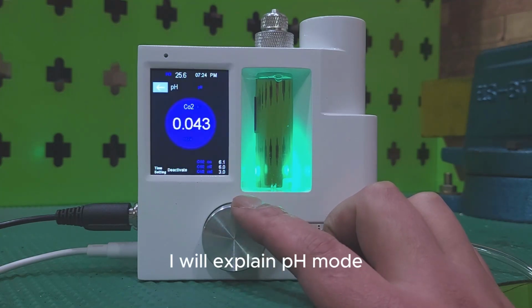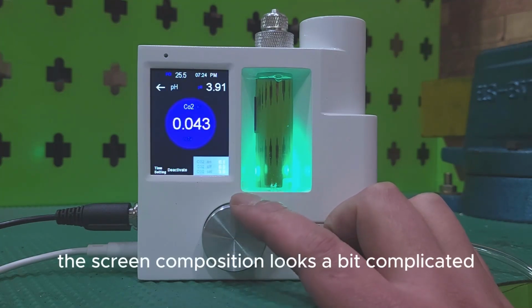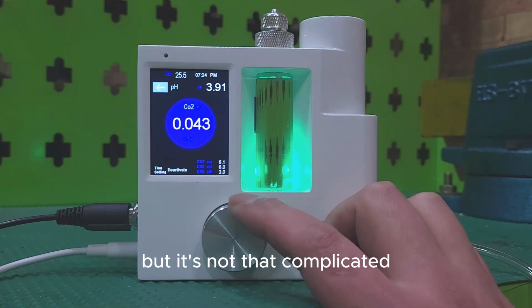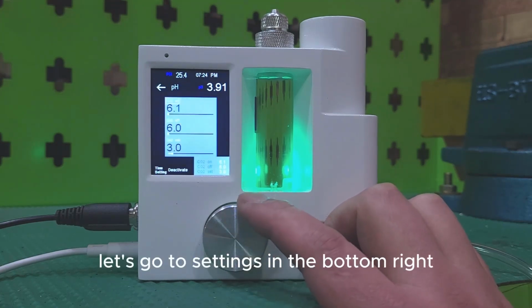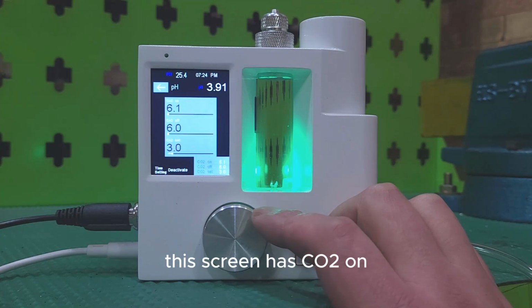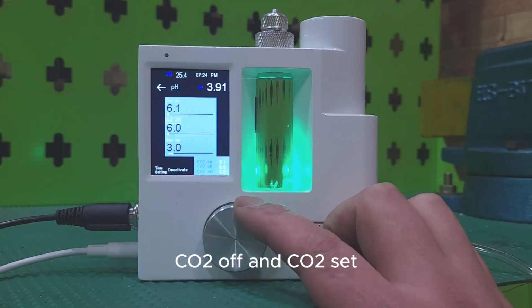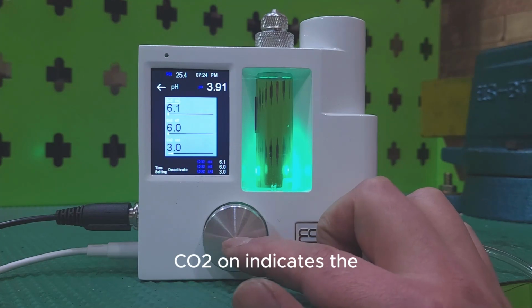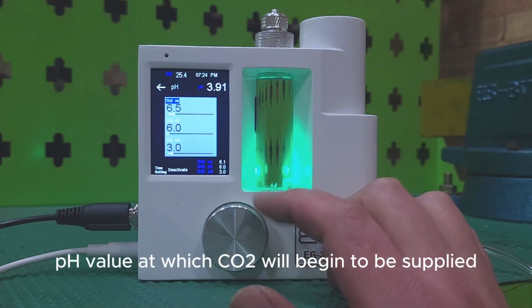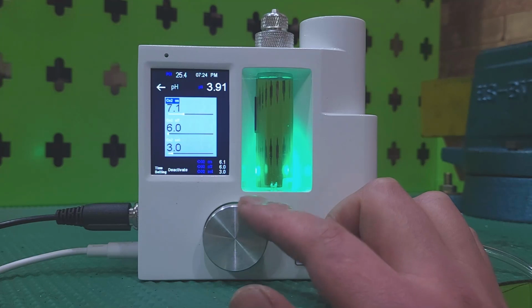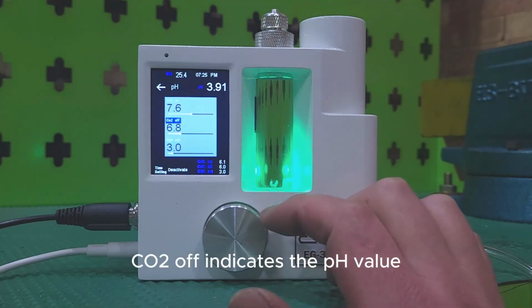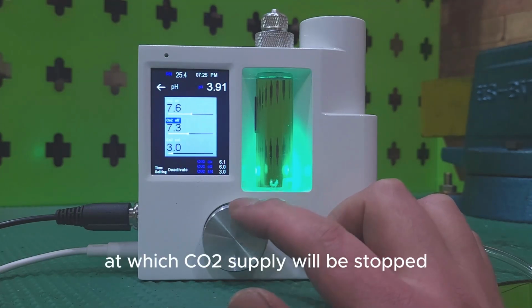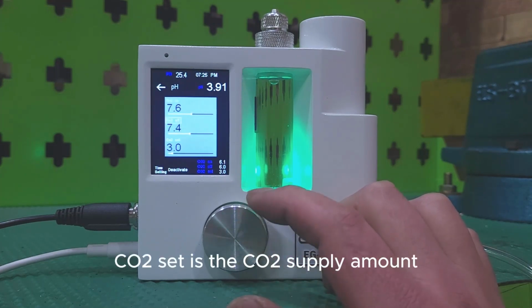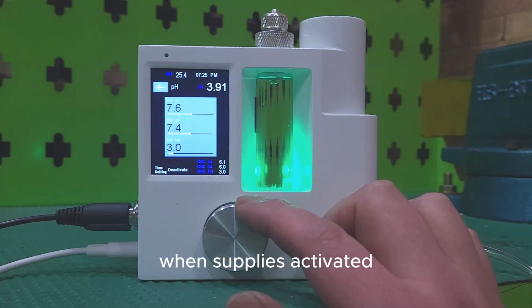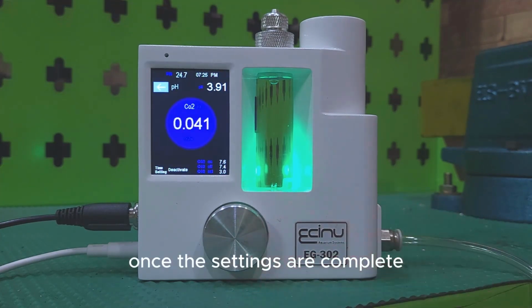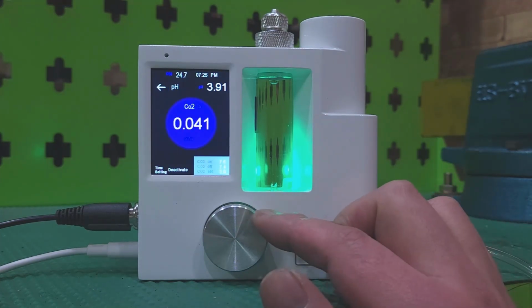I will explain pH mode. The screen composition looks a bit complicated, but it's not that complicated. Let's go to settings in the bottom right and press the dial. This screen has CO2 on, CO2 off, and CO2 set. CO2 on indicates the pH value at which CO2 will begin to be supplied. CO2 off indicates the pH value at which CO2 supply will be stopped. CO2 set is the CO2 supply amount when supply is activated. Once the settings are complete, press the back button to start operating.